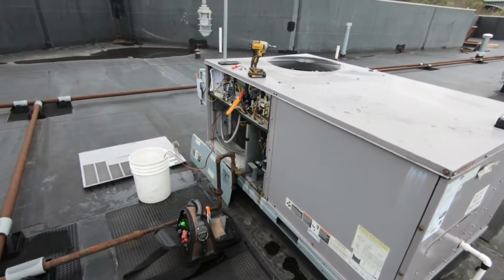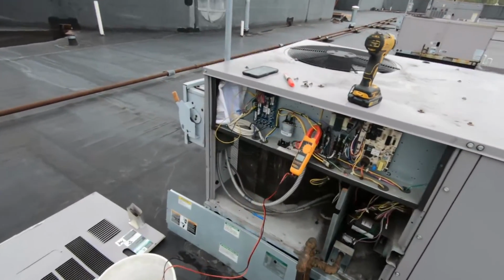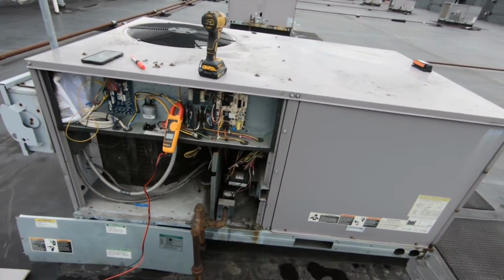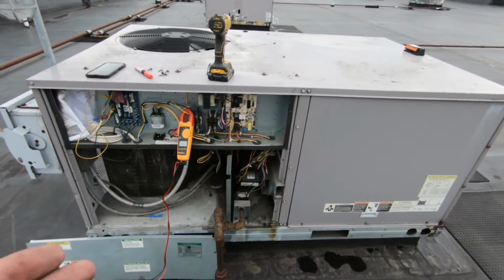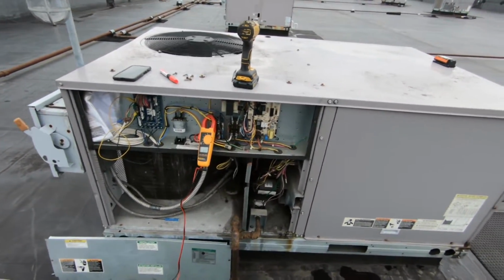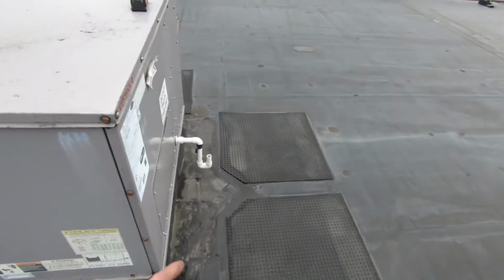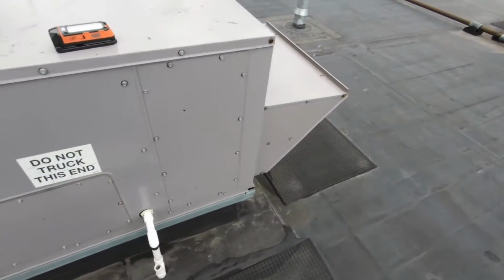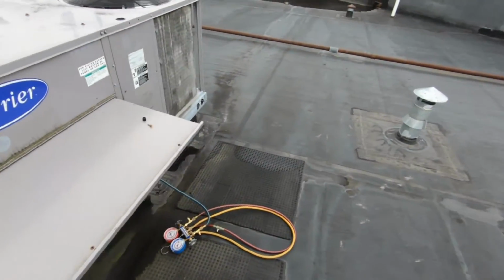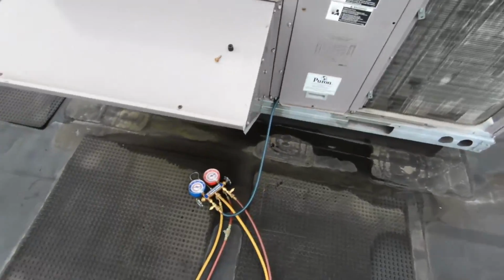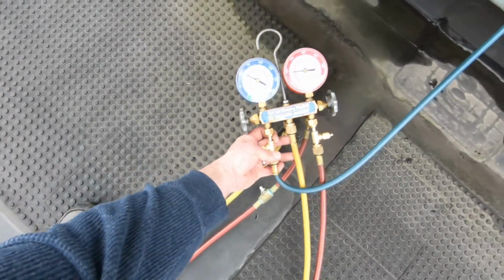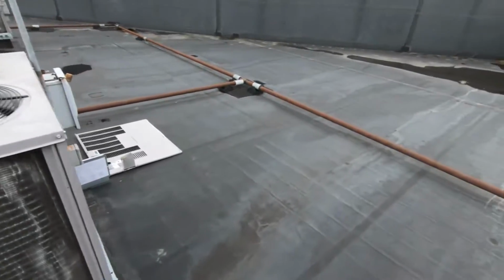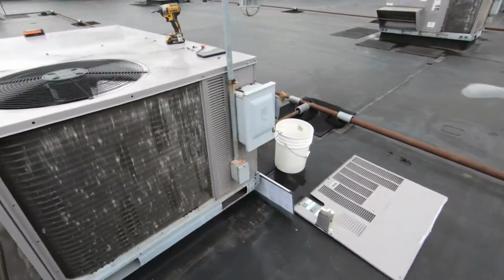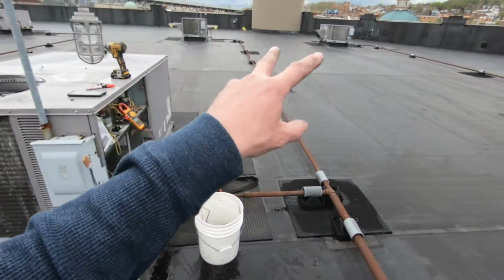No real issues with number 1, besides general maintenance items like filters, belts. Gonna need a couple of contactors, coil cleaning, and a new drain trap. It's got some cracks in it, and we might as well. Pressures are looking good, amp draw on the compressor's looking good, so I'm gonna button this one up, and we're gonna move on to the last 2.